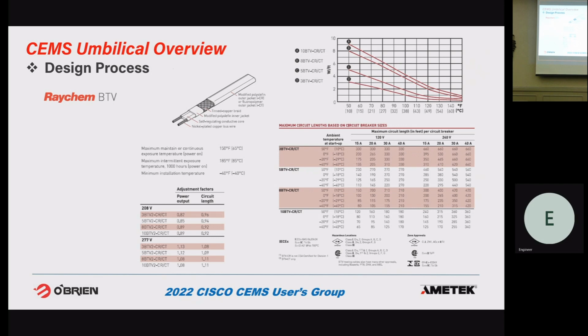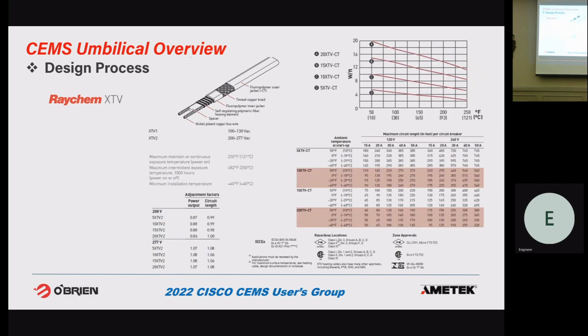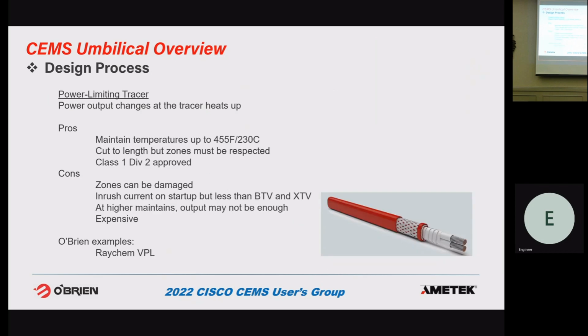So when we go to the next hotter tracer, you'll see the temperature curves are a lot flatter. And as you get to hotter and hotter tracers, those curves are flatter and flatter. So that's the next one. XTV can maintain up to 250F. And like I said, there's one more I don't have on the slide, but it's an HTV, can maintain up to 400F. But at 400F, it's not putting out much power, so we're not generally able to use it for temperatures above about 150F, just not putting much power output.